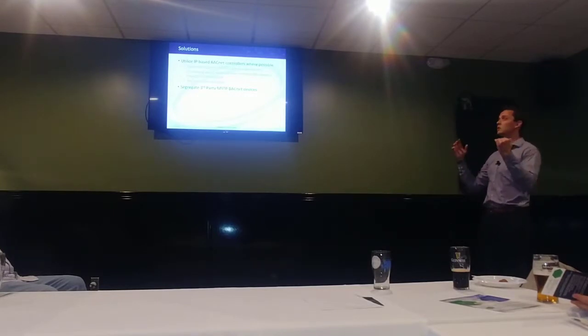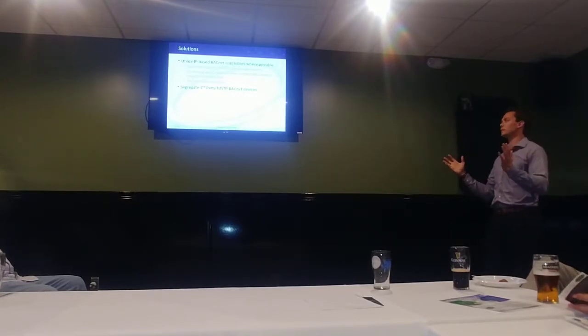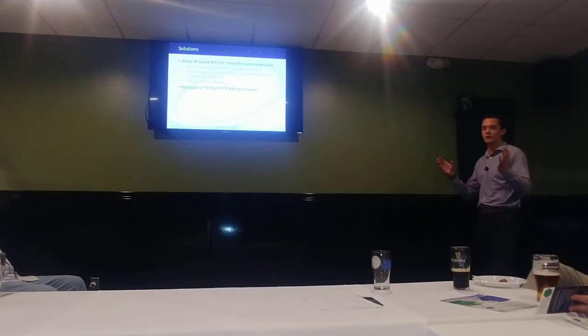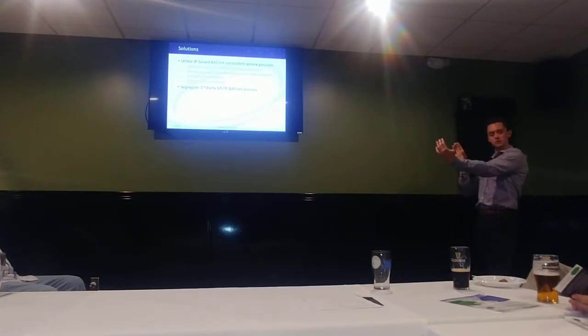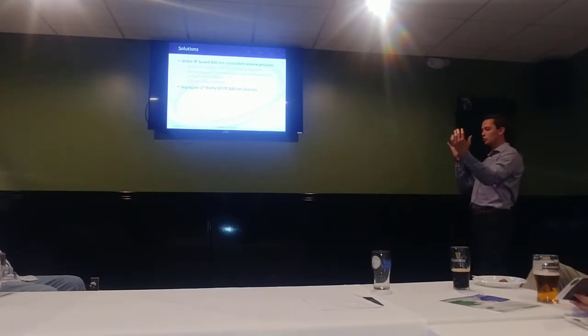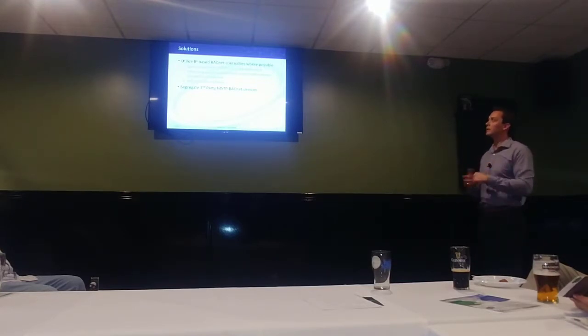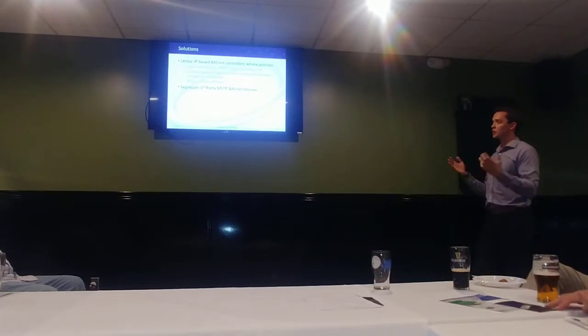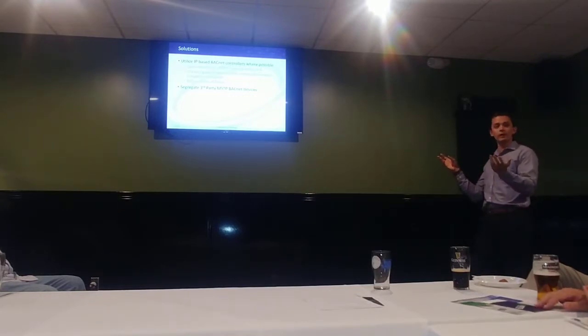So we decided to utilize IP controllers where possible. From a speed standpoint, this was paramount in making sure that we didn't have those lags. We would use basically one system level controller to control 2 to 3 suites, and all those points would go up to this one system controller from an IP standpoint. In doing that, it also reduced the number of points of failure that we would have in the rooms.